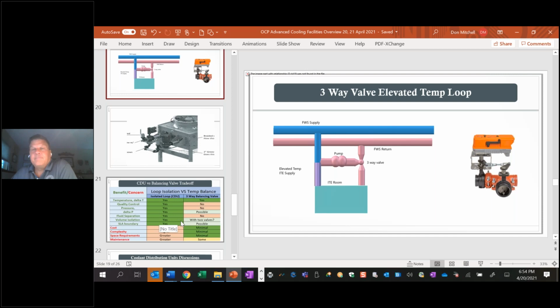But with that setup, I'm not sure that's piped up correctly, because if you're modulating the three-way valve to bypass a certain amount of flow back to the main system or back to the CDU loop, that means your pump has to match that bypass GPM or flow rate. So now you can control the pump flow rate, and if you have flow rate to match, that seems a little complicated to do.